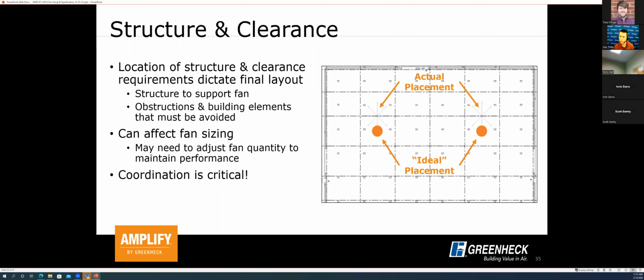Things like that become more critical once you've identified how many fans, what diameter, and your performance level for the space. There are a lot of clearance requirements for HVLS fans. I won't go into all of the details here, but just a few quick things to be aware of. There are safety clearances around the blades to make sure we don't come into contact with an obstruction. There are clearance requirements to other fans, walls, and other HVAC equipment, to make sure we don't have any negative interaction between the airflow of the HVLS fan and other equipment or other parts of the building. And there are clearance requirements to make sure you're not creating some other negative interaction in the space with lighting or other building features.